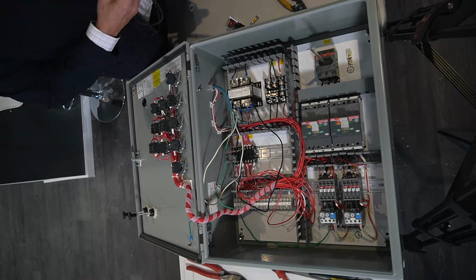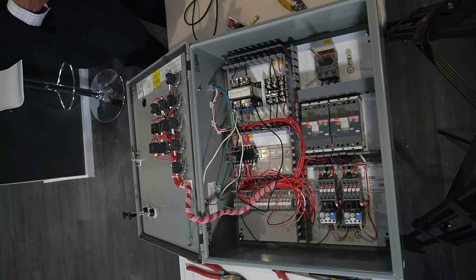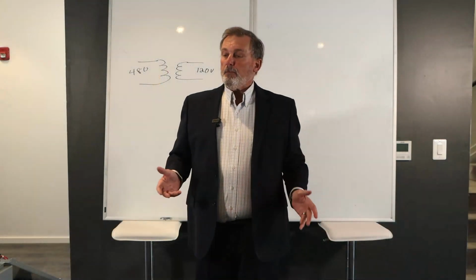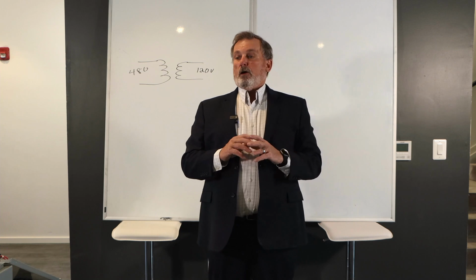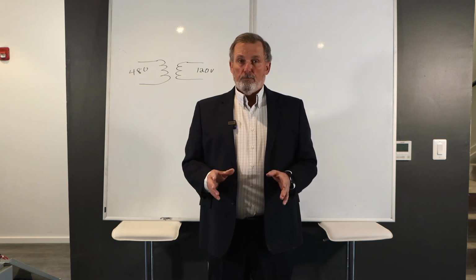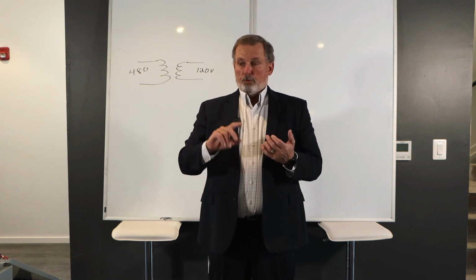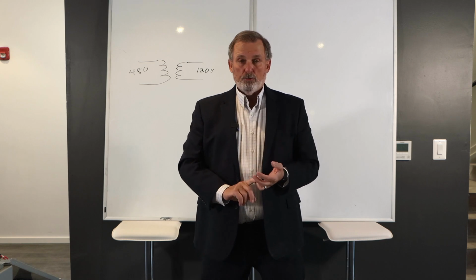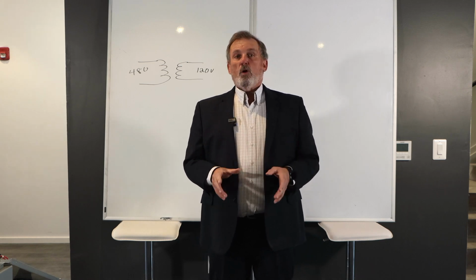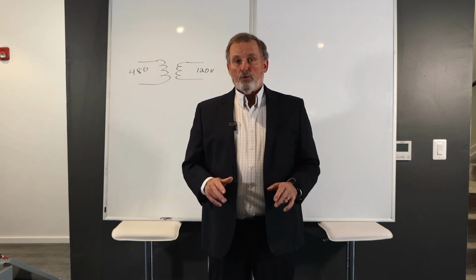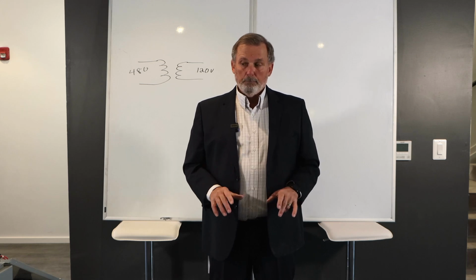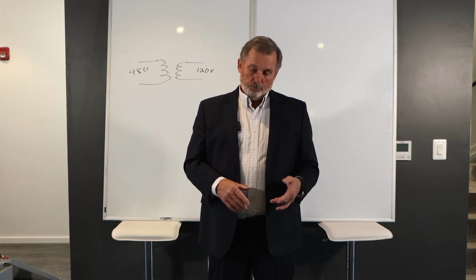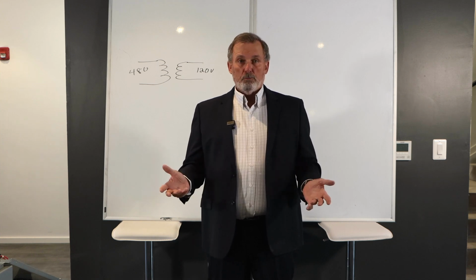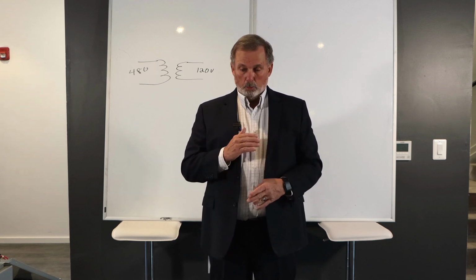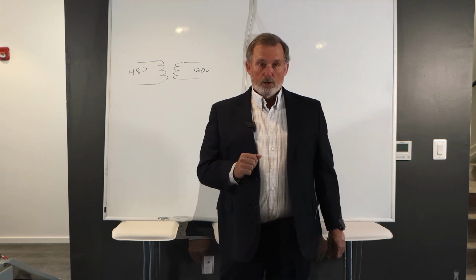That's what we use a transformer for, and this is how we derive that safe operating voltage for all of our operating equipment. It's our safe voltage for limit switches, push button switches in the field, where we don't want 480 volts on the controls. We want to use 120 volts specifically, or even 24 volts in some applications to operate the pumps. So take a break and we'll move into the ladder.